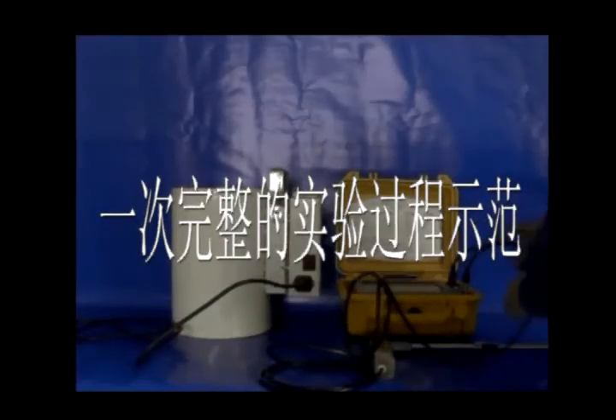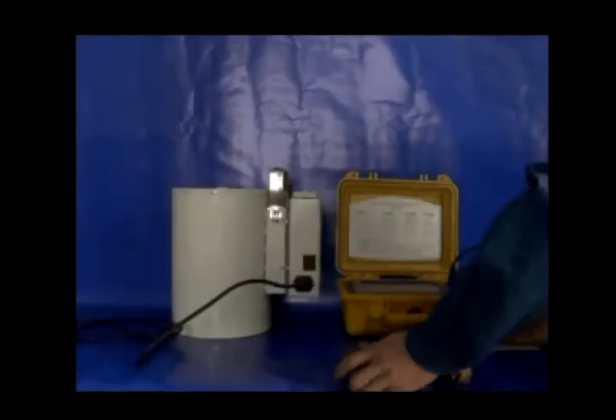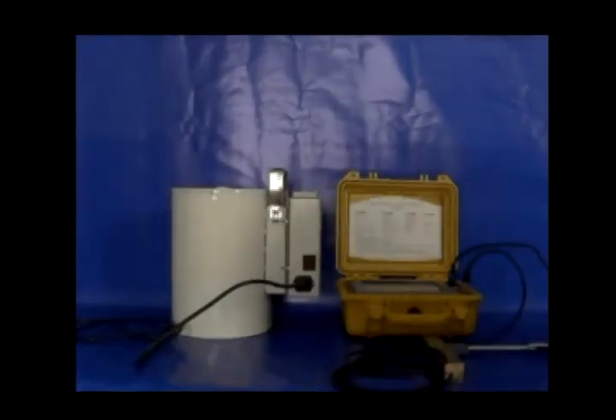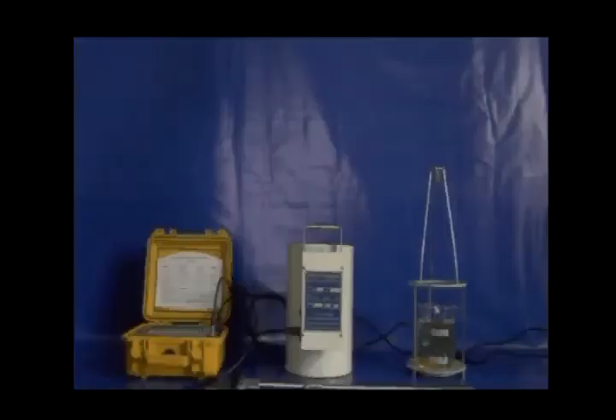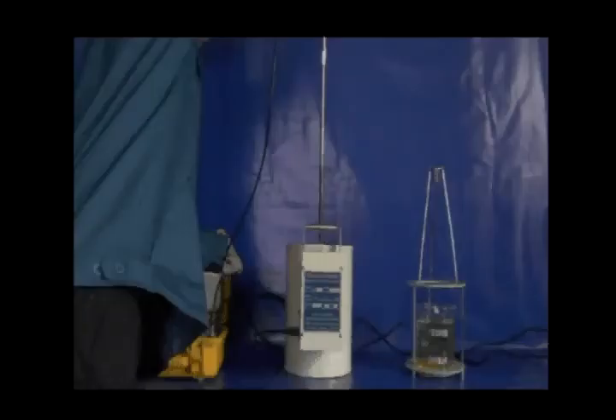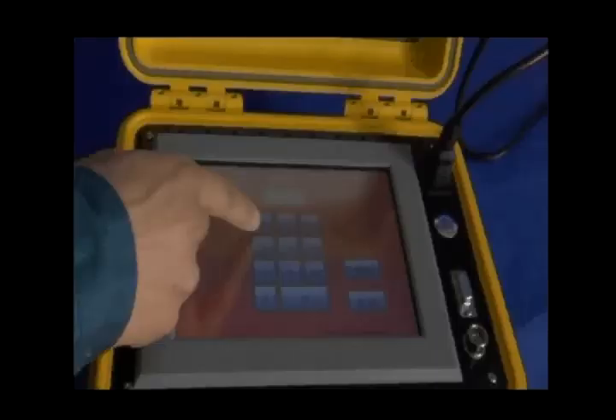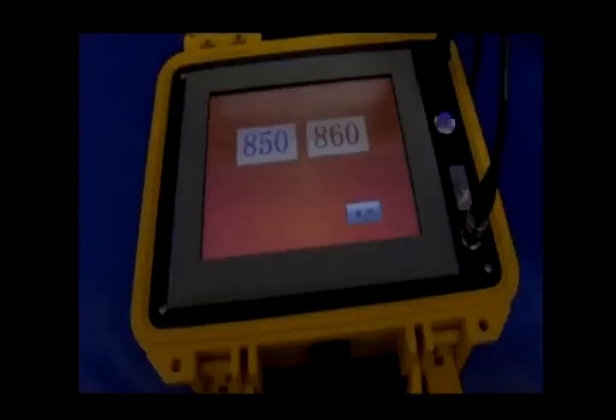Demo of a full experimental operation process. Check all the connecting leads and confirm they are inserted well. Turn on the power switch of the furnace and the recording device. Insert the probe into the furnace vertically. Input the test time, channel number, detection number, and other basic information into the device through the LCD touchscreen of the recording device. Then the recording device starts to record the heating-up process of the probe. When you hear a creaking sound, turn off the power switch of the furnace.